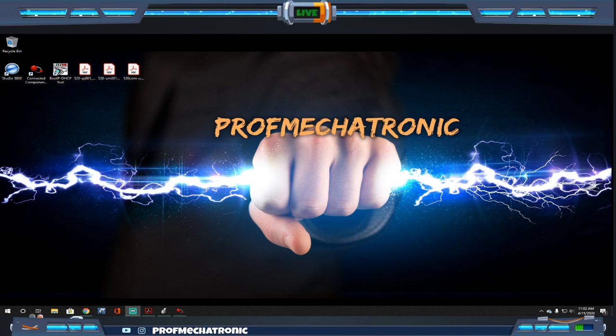VFDs are definitely one of the more common motor control systems out there. They're getting very cheap right now, so you're going to see a lot more VFDs in industry. It's actually almost cheaper now to put in a VFD rather than a forward-reversing motor starter with auxiliary contacts and all the other devices that go with it. You also get more control and more data collection that way.